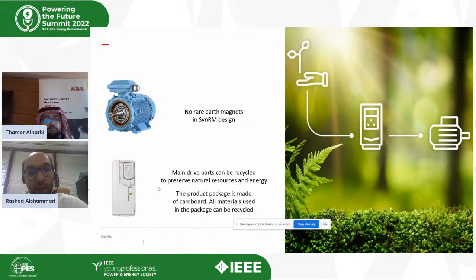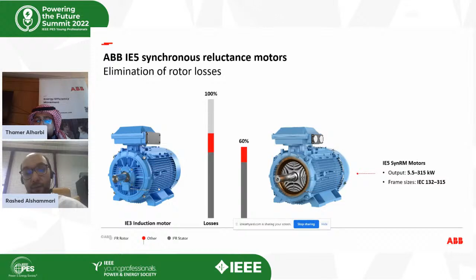Here we can see the difference between the IE3 standard, which people now think is within the highest efficiency, and if you compare IE3 and IE5, the losses - here the losses we have at the top for the rotor losses, then again for other parts, then again for the stator. The good thing in the IE5 synchronous motors is that the rotor is without a bar, meaning there are no losses in the rotor. This means there is no high temperature in the winding of the stator, which increases reliability and reduces temperature for the stator.